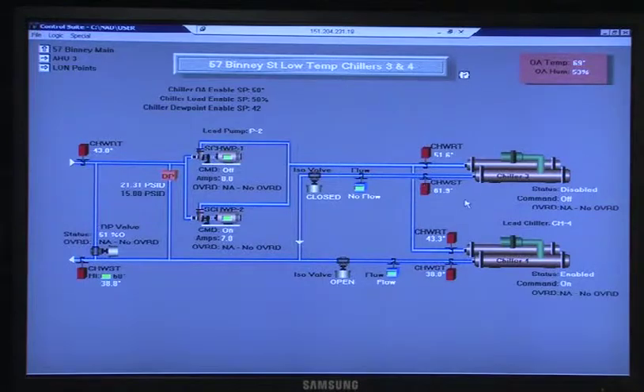We can look at that in a minute, but to get that, you're not going to get that off our chilled water plant. You had to put in a low temperature chiller plant dedicated to get the proper chilled water temperatures across the coil, delivering supply air down to the 7th floor. So what they ended up doing is putting these two chillers in. Okay, same thing as the other one. This is enabled on. This is enabled off.